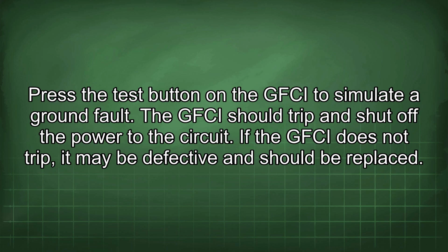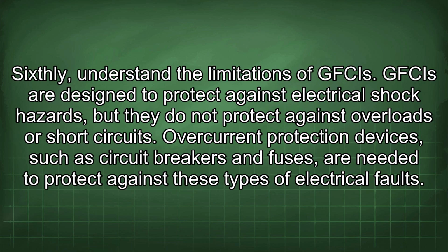The GFCI should trip and shut off the power to the circuit. If the GFCI does not trip, it may be defective and should be replaced. Sixthly, understand the limitations of GFCIs. GFCIs are designed to protect against electrical shock hazards, but they do not protect against overloads or short circuits. Overcurrent protection devices, such as circuit breakers and fuses, are needed to protect against these types of electrical faults.